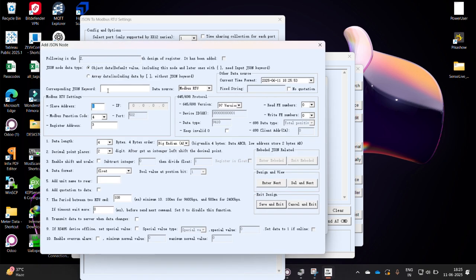Same kind of thing for kVA now. Slave address is 1, and the register address is 5. My data length is the same, 4. Type is float, decimal point 2, and the rest remains as it is. I'm just doing next, and here you can see this is my second parameter.